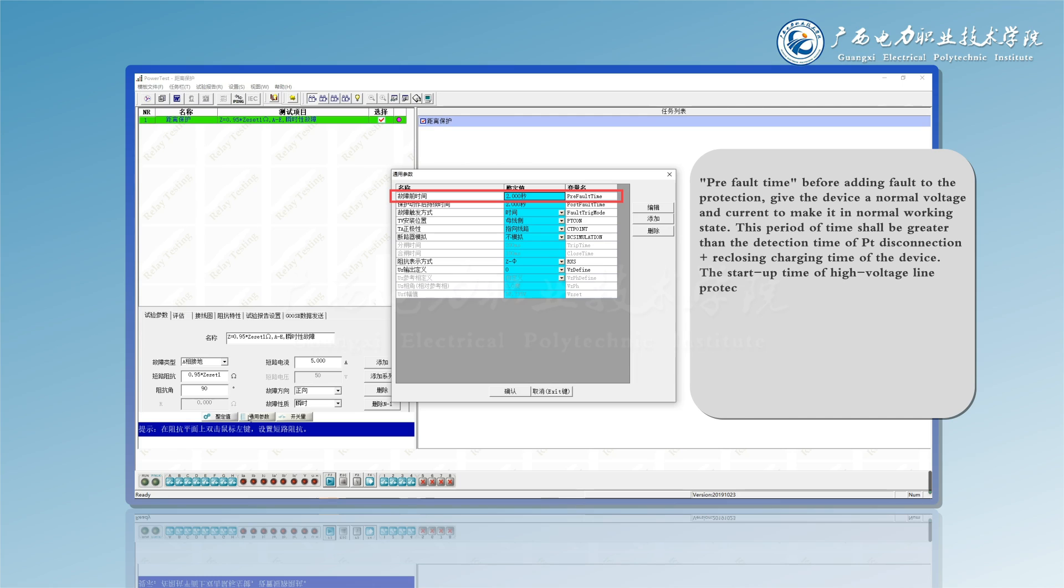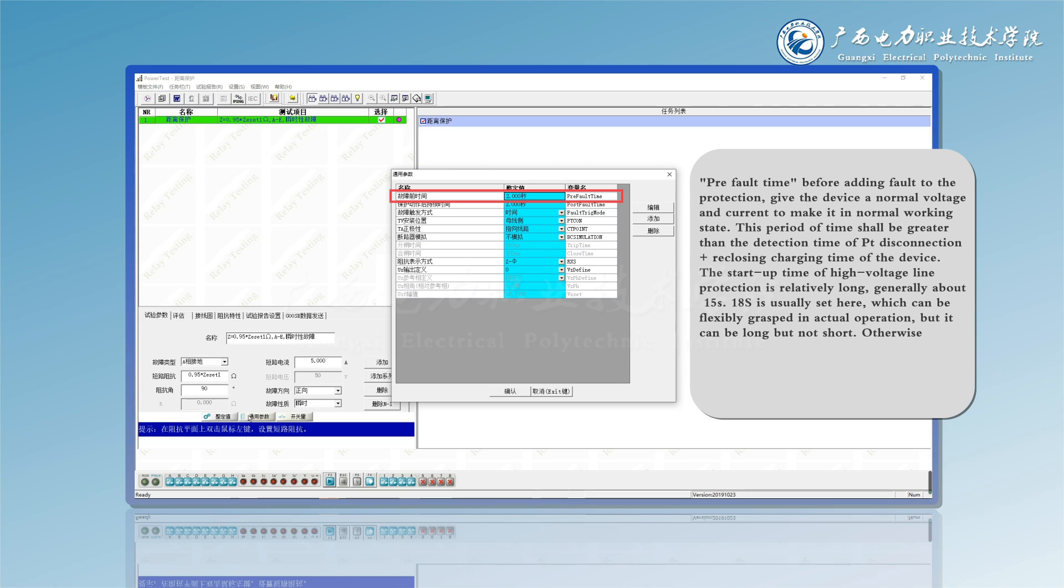The startup time of high voltage line protection is relatively long, generally about 15 to 18S is usually set here, which can be flexibly grasped in actual operation. But it can be long but not short. Otherwise, misoperation of ranging, reclosing failure, and other phenomena will occur when doing distance protection.